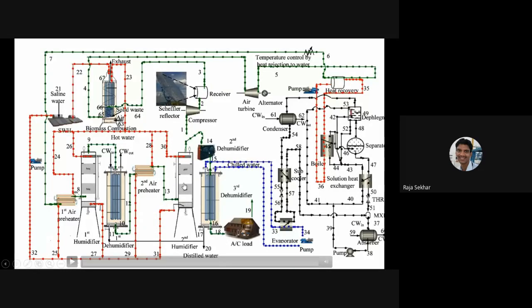We have also obtained condensed potable water. The system which we have designed is able to give around 12 liters per day. Okay, with two dehumidification processes. With the first stage, we are able to get only 5 liters. In the second stage, we are able to get 7 liters. Why? Because the temperature of chilled water is somewhat lower compared to the normal water that we are getting from the overhead tanks. So the delta T available is more, and that's why more condensation is happening at the second dehumidifier.